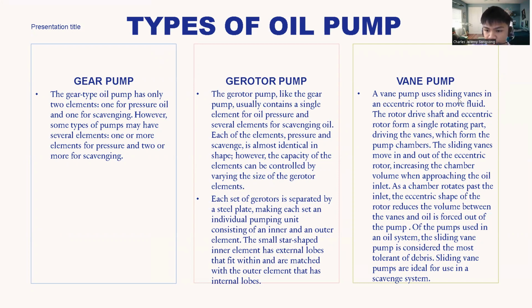Next is the vane pump. A vane pump uses sliding vanes in an eccentric rotor to move fluid. The rotor drive shaft and eccentric rotor form a single rotating part. The driving vanes form the pump chambers. The sliding vanes move in and out of the eccentric rotor, increasing the chamber volume when approaching the oil inlet. As a chamber rotates past the inlet, the eccentric shape of the rotor reduces the volume between the vane and the oil is forced out of the pump.